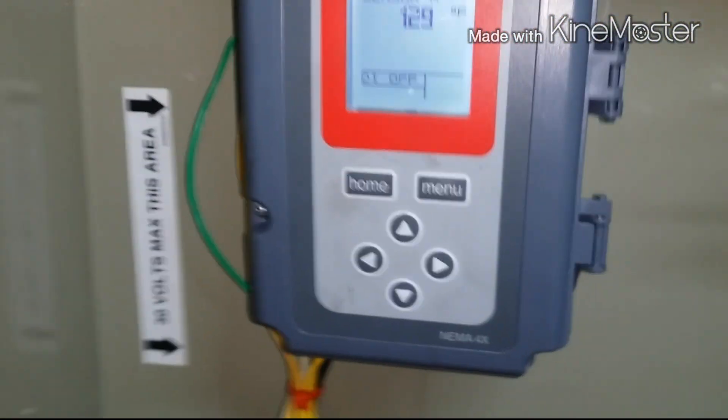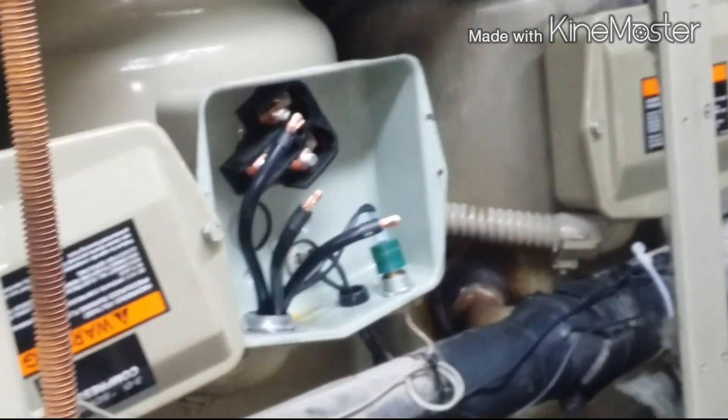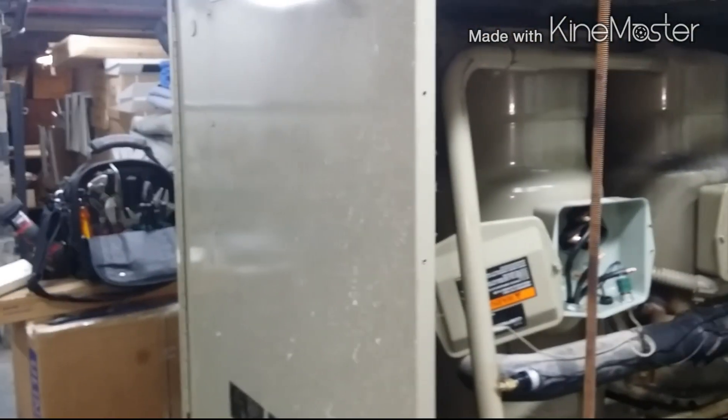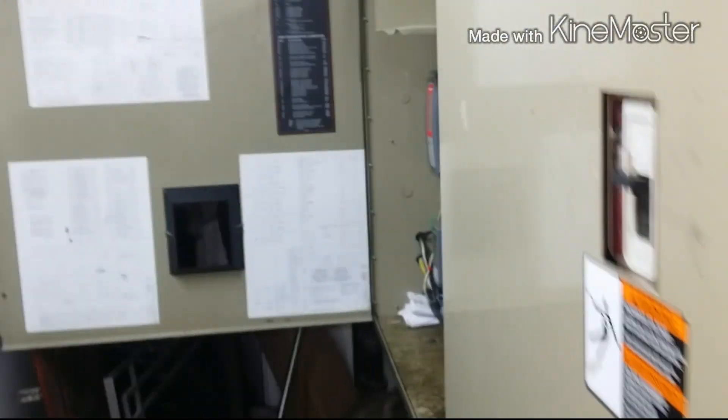One of them is at 129 — same as if your house is 129 degrees, your back pressure will climb up pretty high. I'm going to tape those up, leave it running for now. This thing is supposed to get changed out eventually, probably sometime this year — that's why we did the simple setup here.